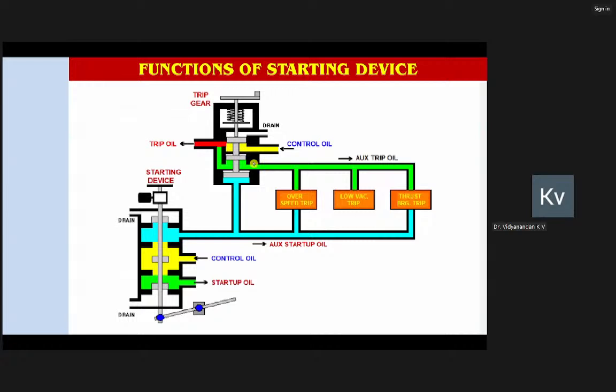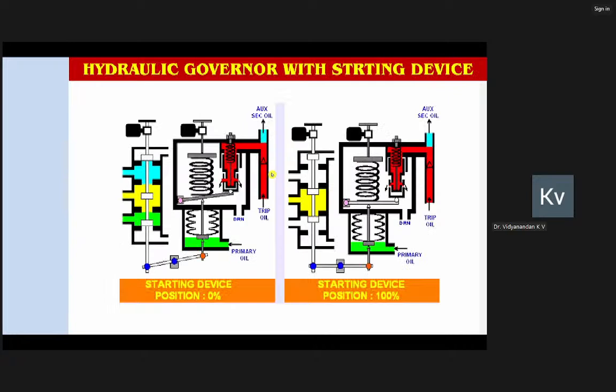So after every turbine trip, we have to re-establish the trip oil, and for that, in your KWU turbine, the Siemens turbine, you have the starting device, and you have to bring the starting device down to 0. With that, the auxiliary startup oil will build up, and that will enable the trip gear to change the port position. With that, the control oil will develop as the trip oil. And in case of your 500 or 250 megawatt, you have auxiliary trip oil as well, which is connected to the individual protective devices. So this is the way the trip gear, the starting device, and the hydraulic governor are interconnected.